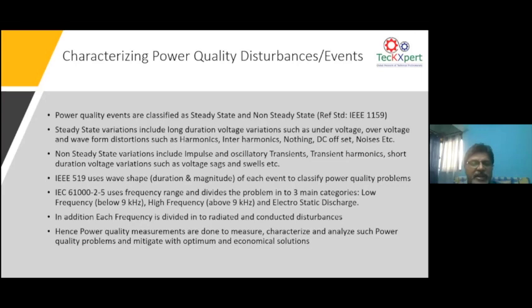There are IEC and IEEE standards which explain how to characterize or interpret these steady state and non-steady state distortions. IEEE 519, as we all know, is a standard which covers harmonics. Harmonics you see only in a waveform, whether a voltage waveform or a current waveform. It is the wave shape that is affected when harmonics are in the system. Other power quality standards like IEC 61000 look at harmonics in terms of frequencies. For example, you can have low frequency, high frequency, as well as electrostatic discharge. So when characterizing power quality, it has steady state, it has non-steady state, and IEEE 519 defines the harmonics or wave shape part.